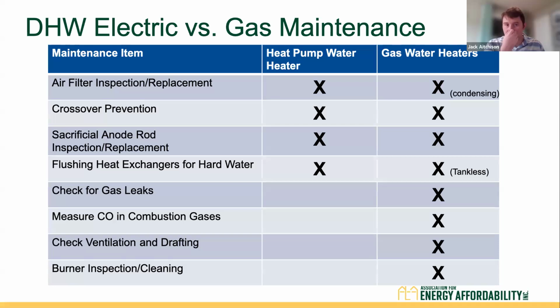Next slide, please. So, DHW electric versus gas maintenance. On a heat pump water heater, you have an air filter. Gas water heaters, if you have a condensing gas water heater, you'll have an air filter. Crossover prevention, really you should be doing this for both. However, it's going to affect your heat pump water heater's efficiency more. Sacrificial anode rod, this is a piece of equipment that is in every storage tank. So regardless of whether it's gas water heating or heat pump water heating, you're going to have to inspect that. Flushing heat exchangers for hard water: like I said, tankless gas water heaters are disproportionately affected by hard water, than heat pump water heaters. You don't really need to do too much hard water consideration when you have a boiler or a tank type water heater, or I guess not as much. And then you have all of your gas specific things like checking for gas leaks, measuring carbon monoxide, checking ventilation and drafting, and burner inspection and cleaning.